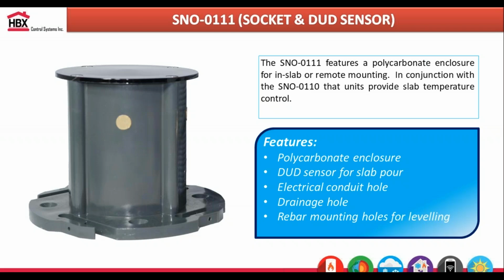It can also get scratched and dented, and it doesn't really matter to a certain point. Obviously, if guys were to chip away at the sensor, that may cause damage. We do provide a drainage hole at the bottom of that socket as well, so if water were to get into it, it really doesn't matter. Water has somewhere to go, but we also advise that you provide some drainage underneath the sensor, because we don't want water puddling in there and then freezing, which could cause damage later on to that optical sensor and also to your concrete and asphalt.